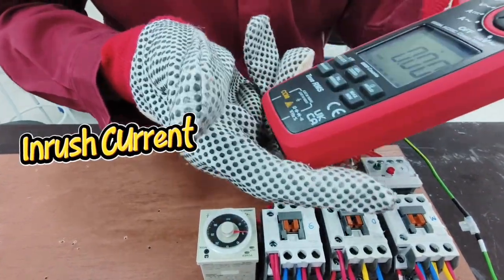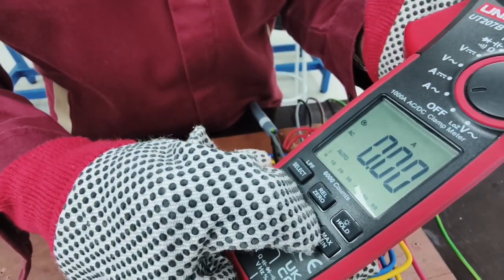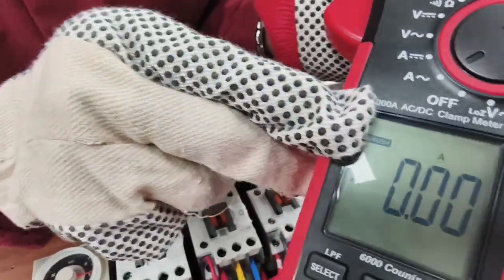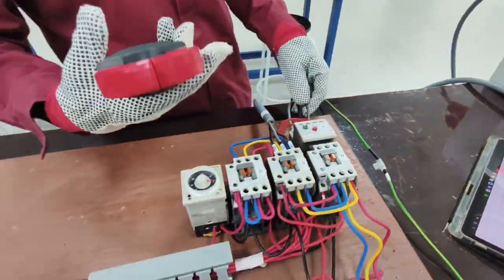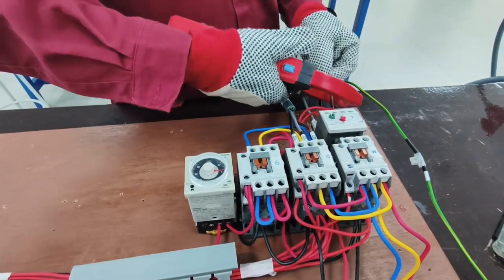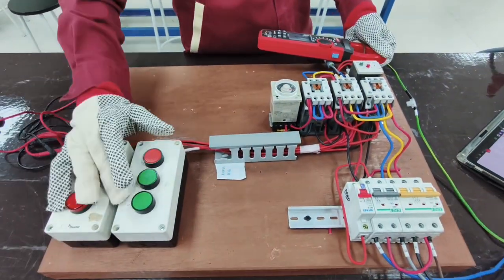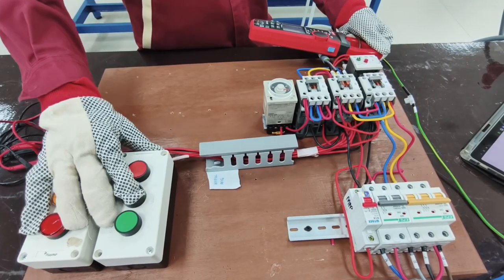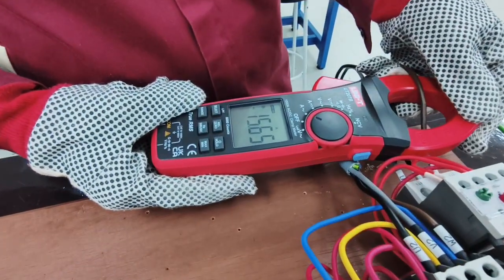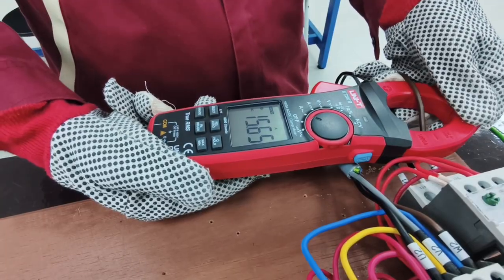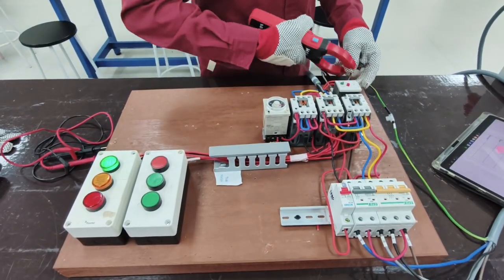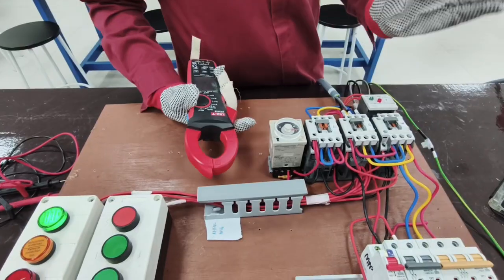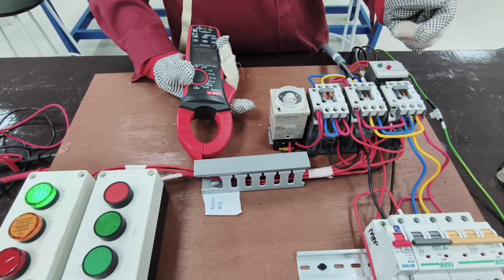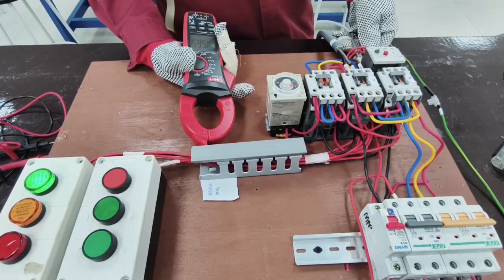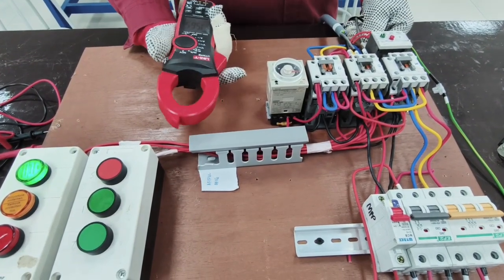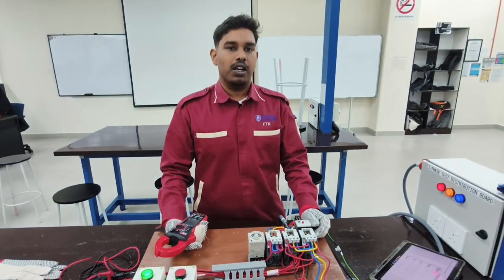We also have a feature which is inrush current. To take inrush current, we just push this inrush and hold it. Then it shows inrush here. We just clamp it on the line we want to take, and then we start the circuit. Here we get 15.65 amp, which is so high. The inrush current happens because when our motor is static and starts to turn on, it will consume a lot of current to make it rotate. So that is our inrush current. That's all the readings that we can take.